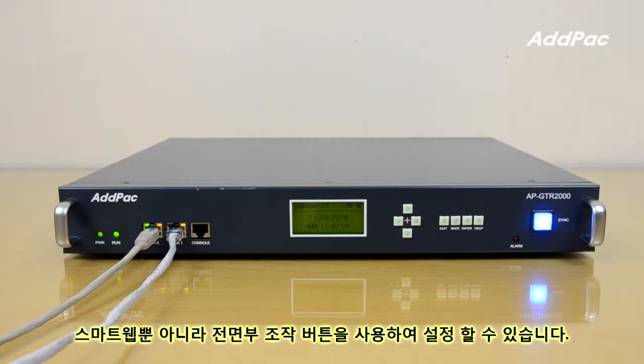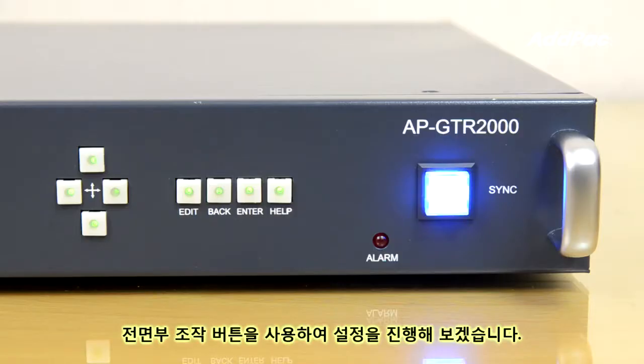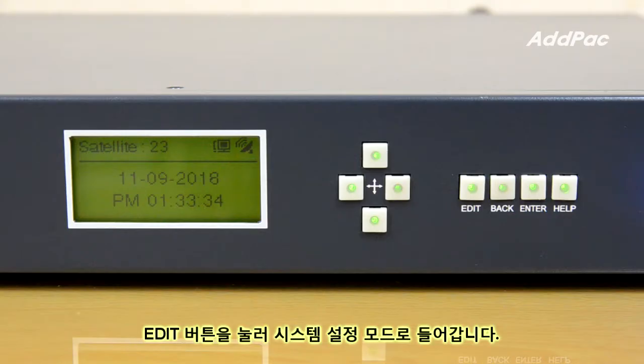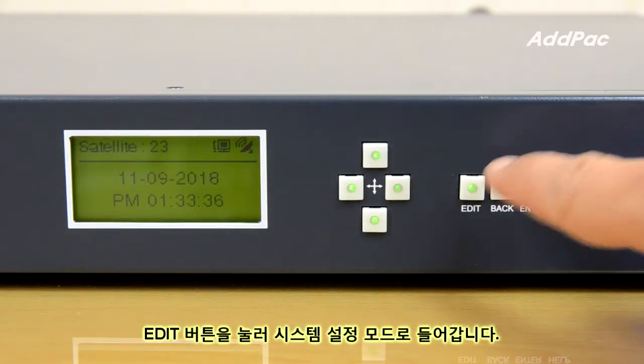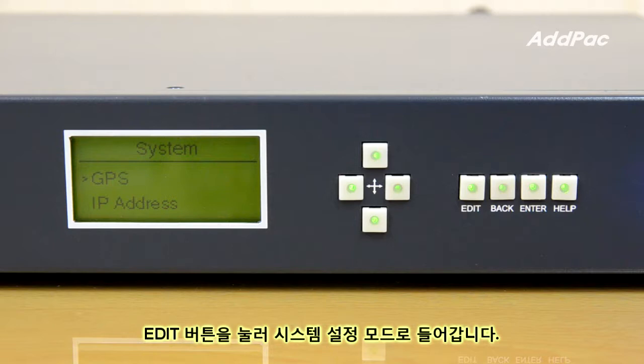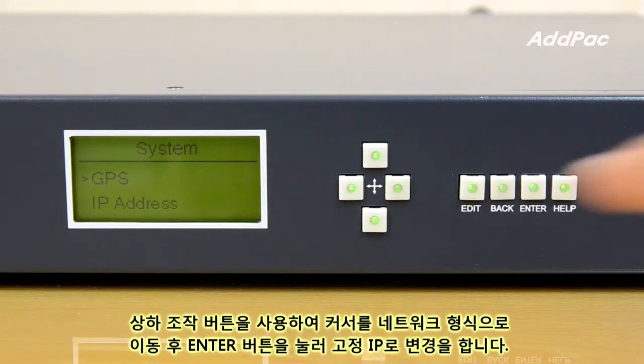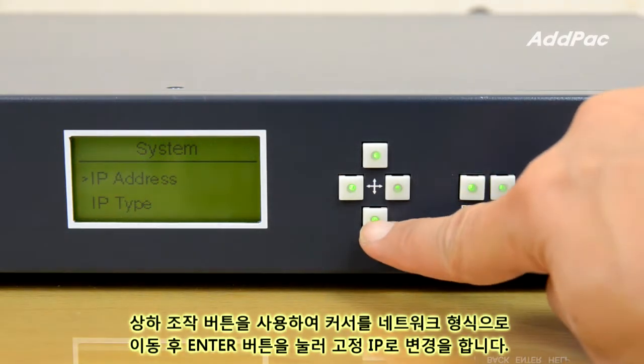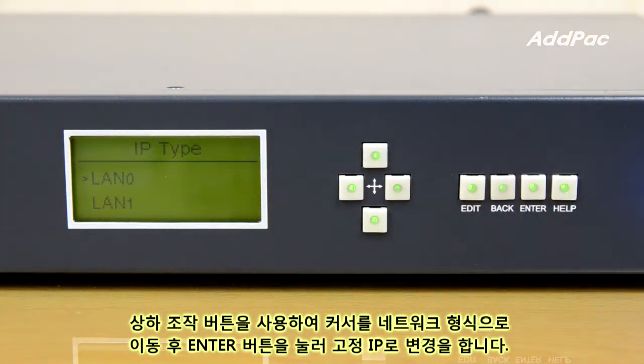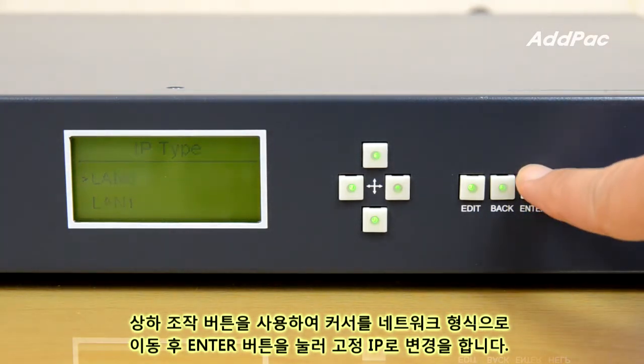You can set it simply using the buttons on the front side as well as Smart Web. Let me start to set using the buttons on the front side of the device. Access system set mode by clicking the edit button. Change to static IP by clicking the enter button after moving the cursor to network type using the up and down buttons.